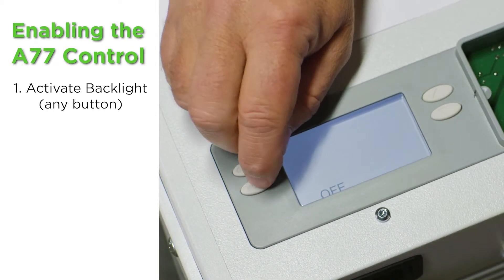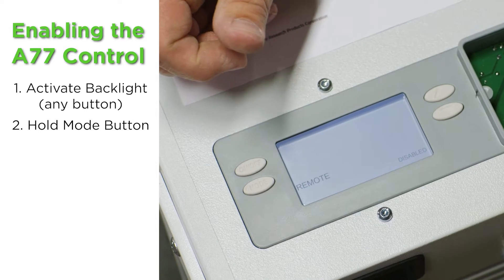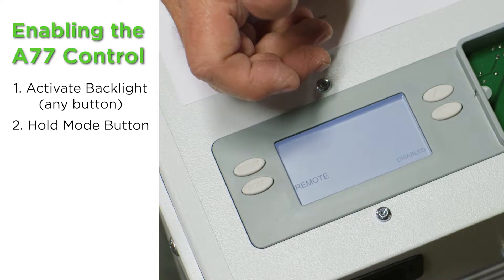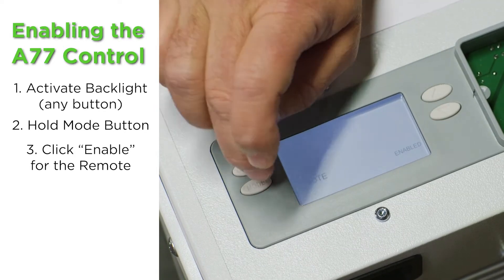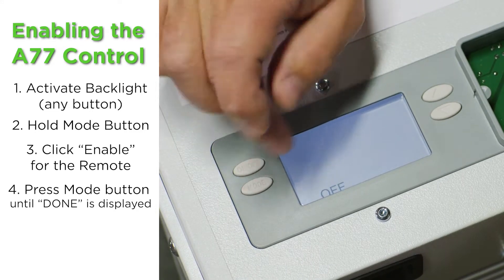With the light on, we're going to hold the mode button down for approximately 15 seconds. Now we're in the installer setup menu, and the very first thing it asks is if we have a remote — which is what we just wired up. It says 'disabled,' so I'm going to push it until it says 'enabled,' then push the mode button repeatedly until it says 'done' on the screen.